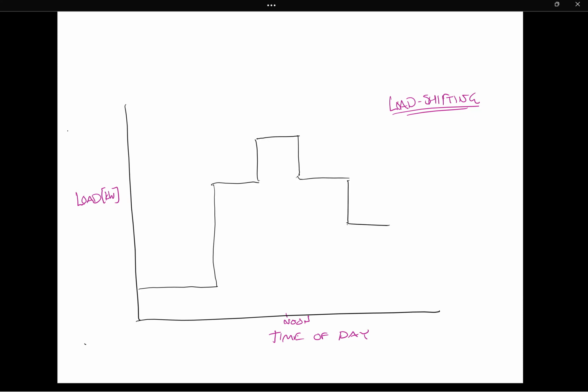So I'm drawing that load situation again, where this is 11 p.m., this is midnight, and this was 250 kilowatts. This is around 750 kilowatts, and we were peaking at 1,000, so we had to buy a 1,000 kilowatt chiller for a conventional air conditioning system. But we're looking at ways of using thermal energy storage to shift some of this now. So that's our building load.